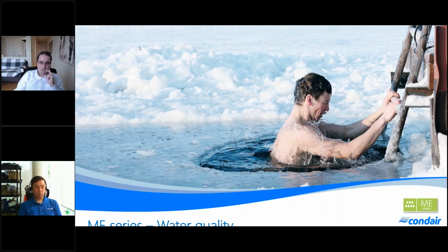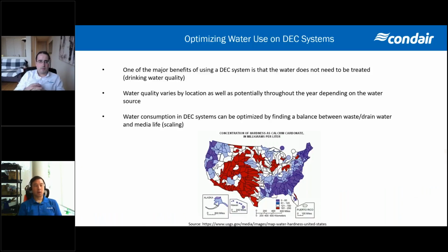So with that, we'll jump right into water quality here, and that's something fairly new that we've started looking at because of this request for maximizing the efficiencies on the water side for these types of systems. As I'd mentioned, one of the big benefits to using a direct evaporative media system is that water does not need to be treated. So you don't have to go through an RO system, you don't have to go through a DI system, so you don't have any incurred water losses right off the bat. The only quality that we require is a minimum drinking water quality for these types of systems.